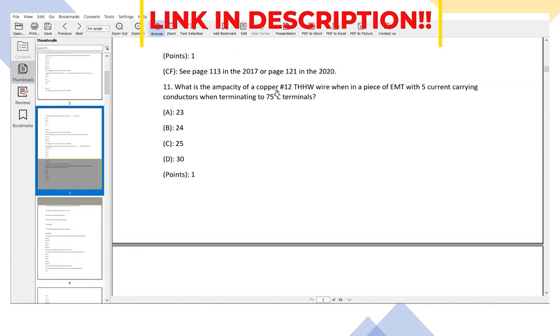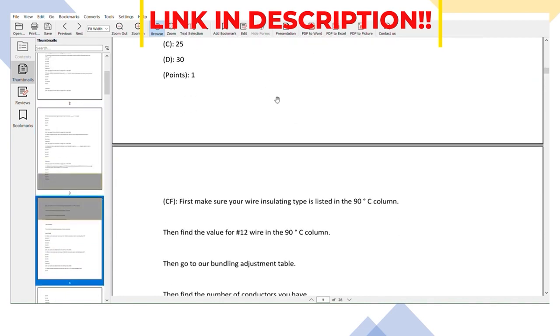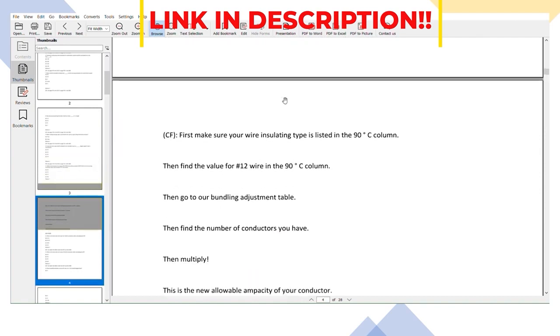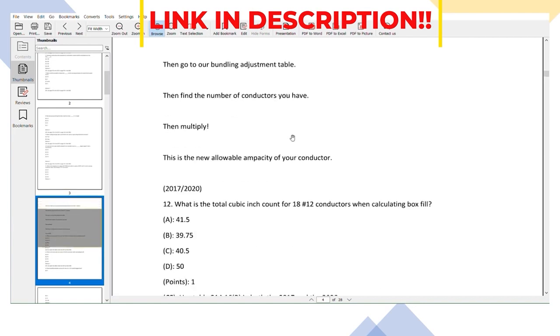Let's look at this one here: the ampacity of a number 12 conductor with five current carrying conductors. I go step by step by step explaining exactly what to do, how to come to that process. So some of them are specific code references and some of them are very detailed step by step processes in order to help you guys along the way.